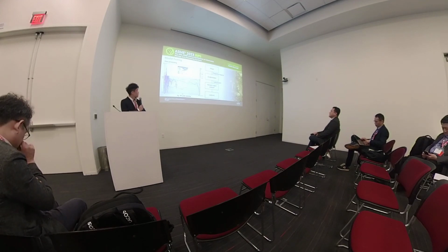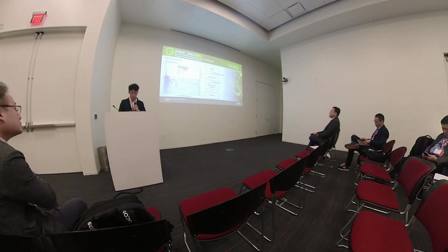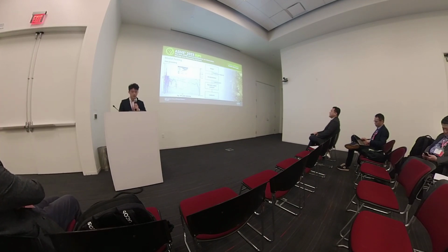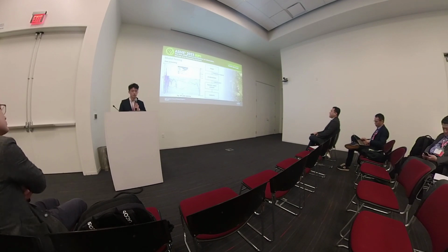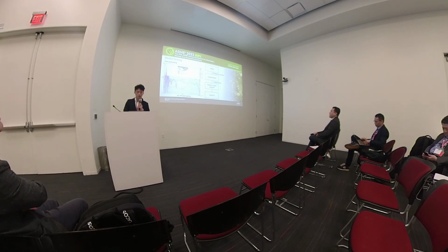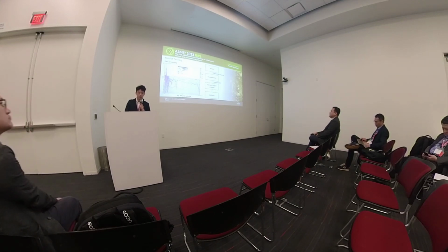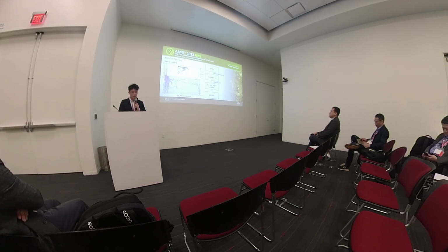The modal test collects the frequency response from the accelerometer into the dynamic signal analyzer and uses the fast Fourier transform to convert the time domain to the frequency domain. Then we import the data into a software on the computer. On the left side of these slides, I show the frequency response function and how I select the poles to extract the modes. The poles represent the stable modes and how the real modes appear in the frequency domain.